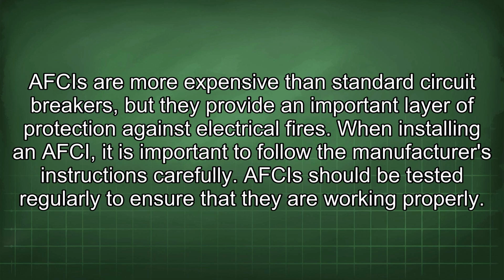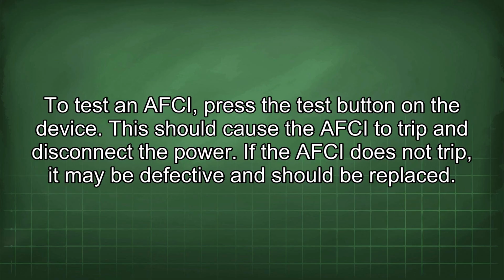AFCIs are more expensive than standard circuit breakers, but they provide an important layer of protection against electrical fires. When installing an AFCI, it is important to follow the manufacturer's instructions carefully. AFCIs should be tested regularly to ensure that they are working properly. To test an AFCI, press the test button on the device. This should cause the AFCI to trip and disconnect the power. If the AFCI does not trip, it may be defective and should be replaced.